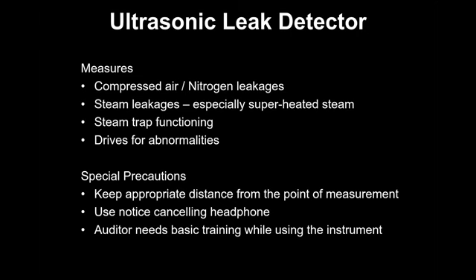It will not quantify. There are some instruments which also quantify and tell you how much the leakage is, but I don't go by that argument, because it's very difficult to quantify. It can tell you whether it's minor or major, a kind of subjective analysis, but it cannot quantify the number. But there are instruments available which will do whatever their algorithm and logic is and tell you the losses through the leakage.